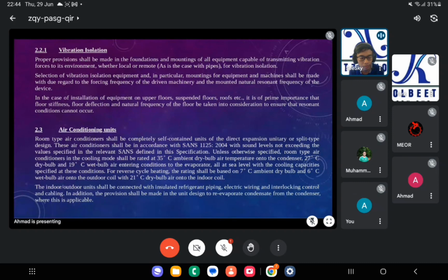all at sea level, with cooling capacity specified at this condition. For reverse cycle heating, the rating shall be based on 7 Celsius ambient dry bulb and 6 Celsius wet bulb onto the outdoor coil, with 21 Celsius dry bulb onto the indoor coil. And the indoor and outdoor unit shall be connected with insulated refrigerant piping, electrical wiring, interlocking control, and cabling. In addition, provision shall be made in the unit design to evaporate condensate from the condenser where applicable.